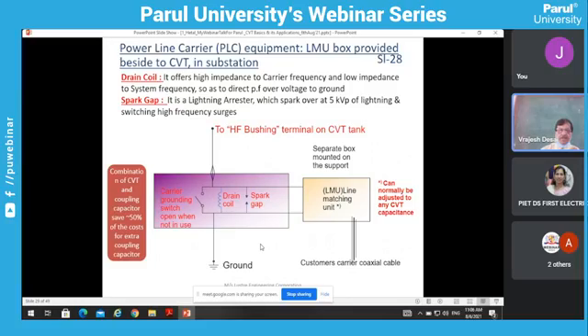Wherever we have a CVT which is used for power line carrier communication, this left side link is open, otherwise it is closed. It has a drain coil and spark gap for protection. Where a high frequency signal is coming, this particular drain coil offers high impedance, and when there is a normal power frequency voltage, it provides a low impedance. So that is how it works. And the spark gap is provided to protect against voltage surges coming to this earth point.